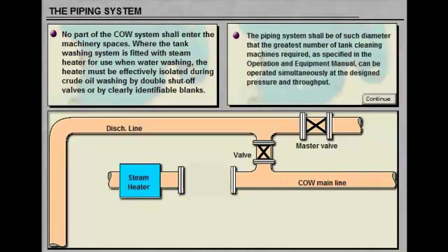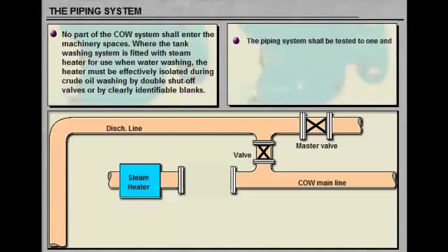The piping system shall be of such diameter that the greatest number of tank cleaning machines required, as specified in the Operation and Equipment Manual, can be operated simultaneously at the designed pressure and throughput. The piping system shall be tested to one and a half times the working pressure after it has been installed on the ship.